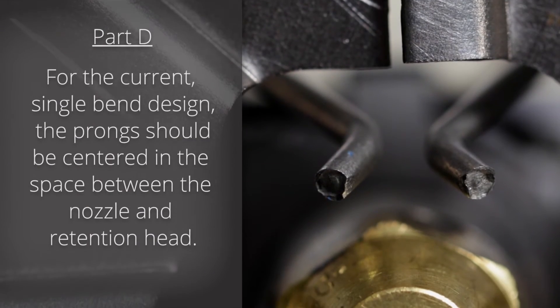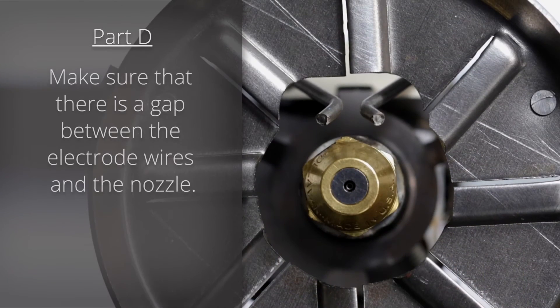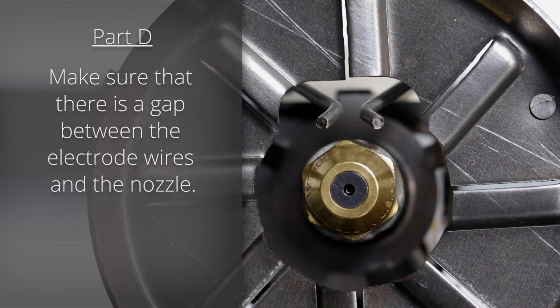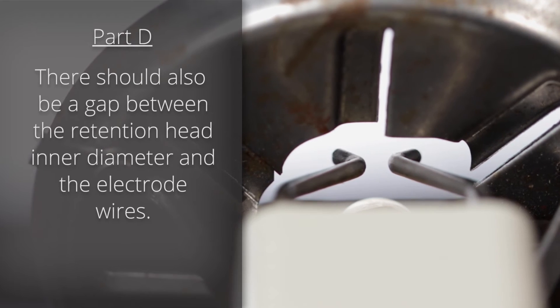For the current single-bend design, the prongs should be centered in the space between the nozzle and retention head. Make sure that there is a gap between the electrode wires and the nozzle. There should also be a gap between the retention head inner diameter and the electrode wires.